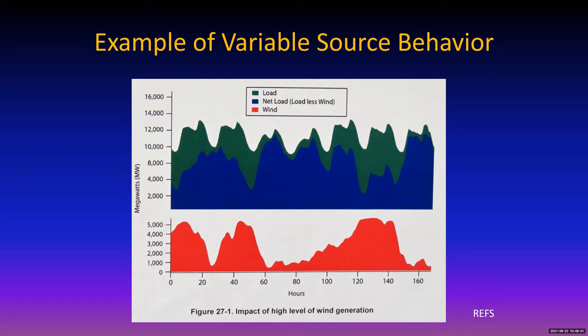So the thing to look at here is the net load, the net load after the wind takes up part of it. And the thing to look at is the slopes on these curves. Note the steep slope on the blue curve compared to the green curve means things turn on and off a whole lot faster. That's something that needs to be dealt with, because the difference between the blue curve and the green curve, right now it's the red that's doing that, but it's the net load that has to be provided by other sources. And those other sources need to be able to come on really fast.